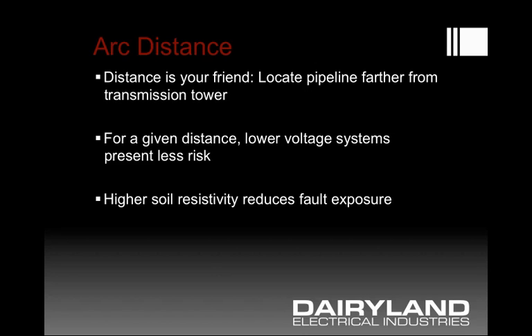What the arc distance graph tells you is that distance is extremely helpful. You would want to locate your pipeline, if you have the choice, further away from a transmission tower to reduce any possibility of arcing. Lower voltage systems, such as distribution power lines, have a lower risk associated with them. But don't be fooled — AC mitigation and AC induction relate to current flow, so there can still be significant induction on a pipe even from a distribution system. Considering just the arc distance problem, lower voltage class systems have lower risk. Also, increased soil resistivity reduces fault exposure, as the soil is not as conductive.